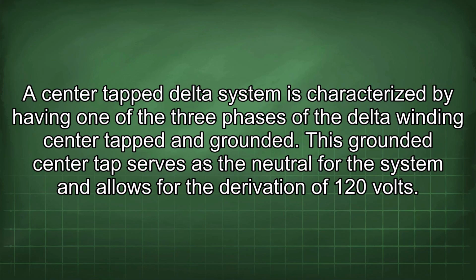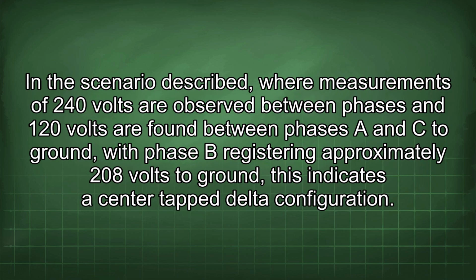A center tap delta system is characterized by having one of the three phases of the delta winding center tapped and grounded. This grounded center tap serves as the neutral for the system and allows for the derivation of 120 volts. In the scenario described, where measurements of 240 volts are observed between phases and 120 volts are found between phases A and C to ground, with phase B registering approximately 208 volts to ground, this indicates a center tap delta configuration.